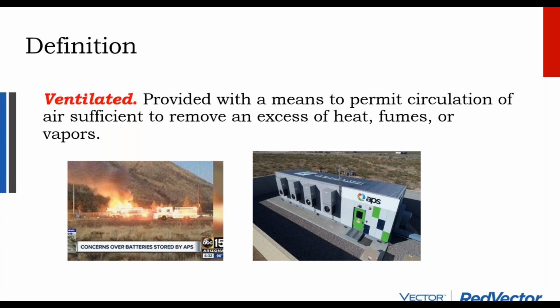And for whatever reason, and I don't know the real details of this, so just hypothetically speaking, if you have ventilation going in your battery room, but it's an emergency and your ventilation is not on some kind of emergency or backup power circuit, and so your ventilation isn't working when the fire is going on, you can get gas accumulation inside that room. And that's exactly what happened in this APS fire. The batteries caught on fire, the room was not ventilating, and the gas accumulated inside the battery container. When the fire department showed up, as soon as they opened the door, the room exploded and it sent a bunch of firemen to the hospital.